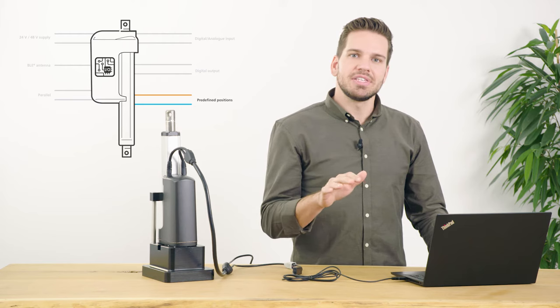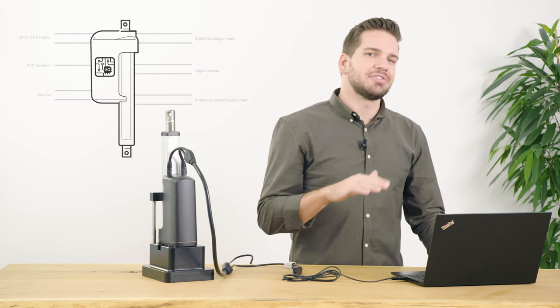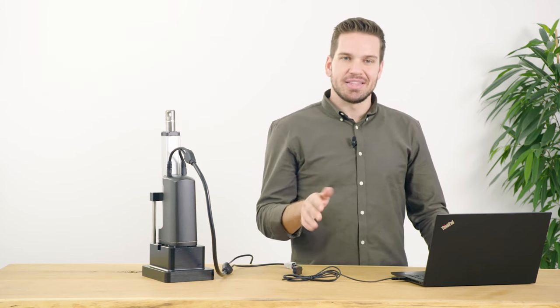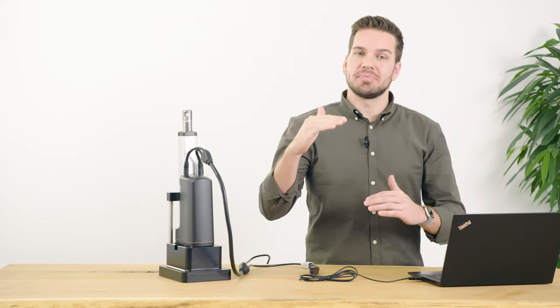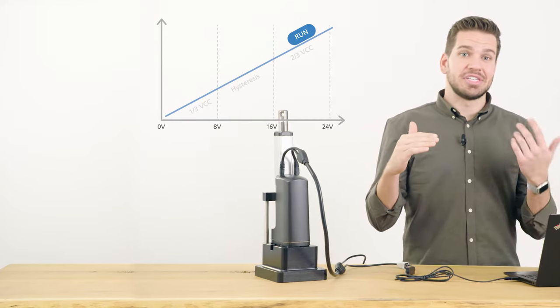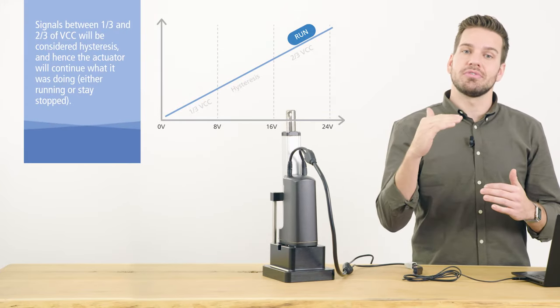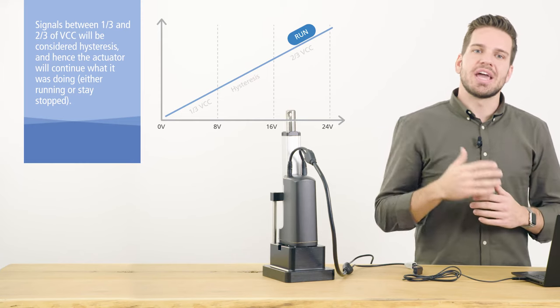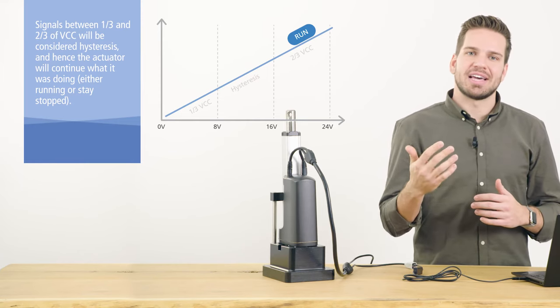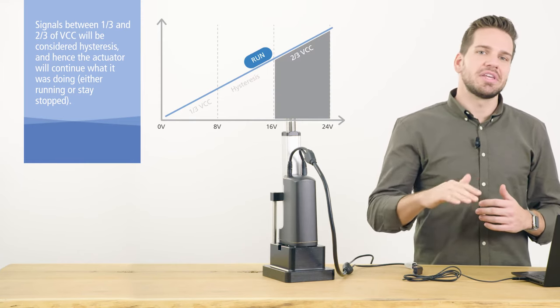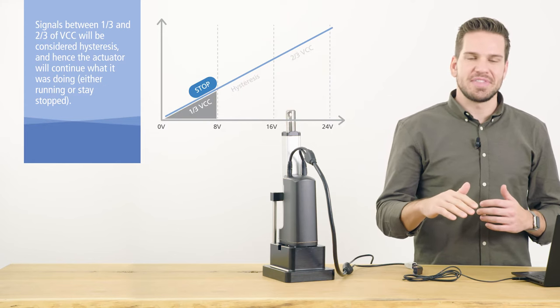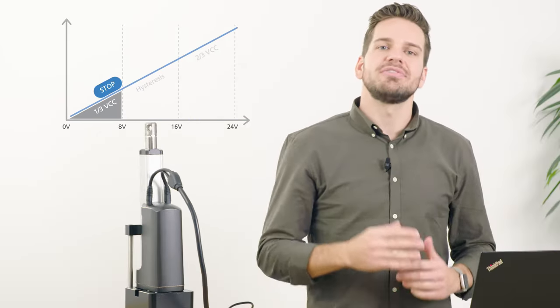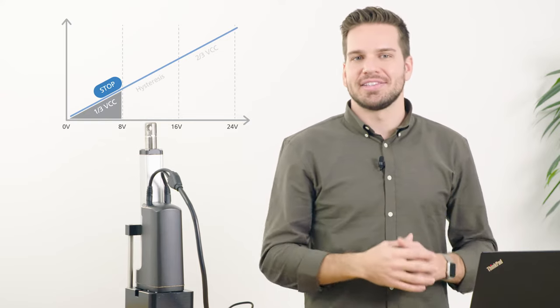All of these input options can be divided into either digital or analog control signals. The digital input detects if a voltage is above or below a specific threshold. If the voltage is higher than two-thirds of 24 volts or 48 volts, the supply voltage, the actuator will detect the digital input as high. If the voltage is lower than a third of the supply voltage, the actuator will detect the input as low. By default, the actuator will only run on a high signal.